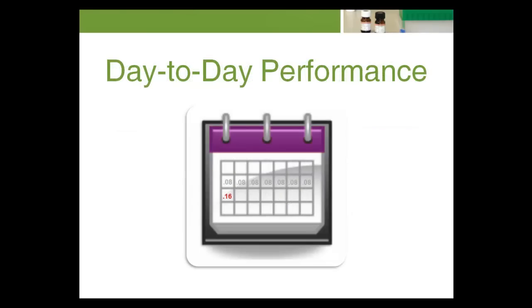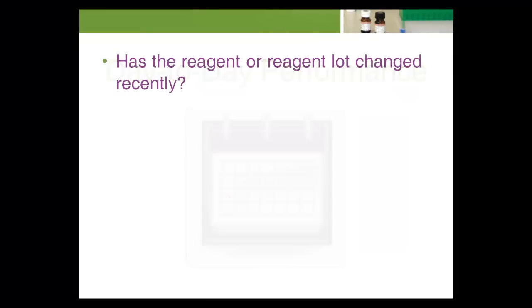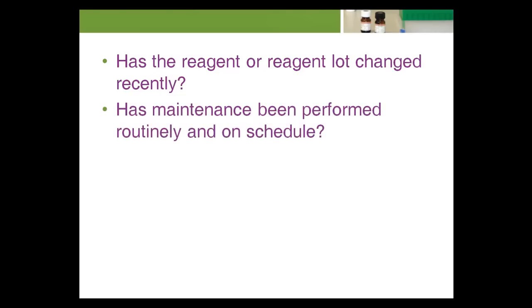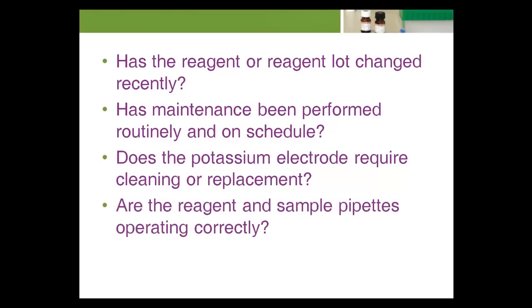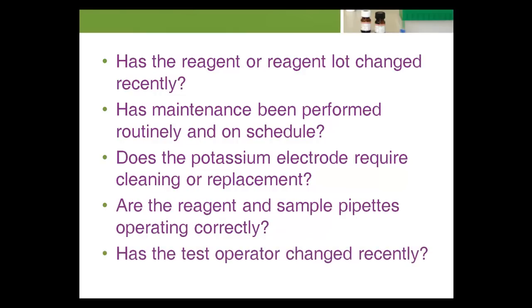Standard deviation may also be used to monitor ongoing day-to-day performance. For instance, if during the next week of testing the standard deviation calculated in the example for the normal potassium control increases from 0.08 to 0.16 millimole per liter, this indicates a serious loss of precision. This instability may be due to a malfunction of the analytical process. Investigation of the test system is necessary, and the following questions should be asked: Has the reagent or reagent lot changed recently? Has maintenance been performed routinely and on schedule? Does the potassium electrode require cleaning or replacement? Are the reagent and sample pipettes operating correctly? Has the test operator changed recently?